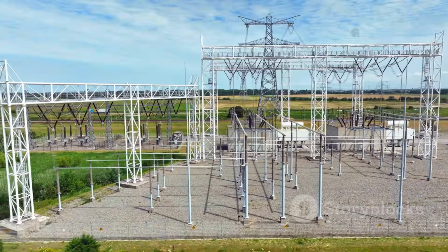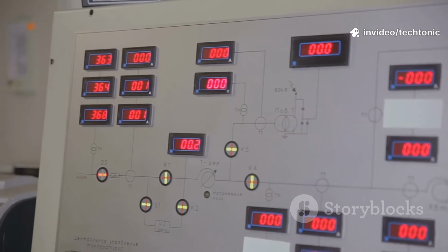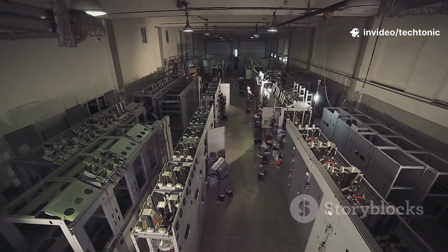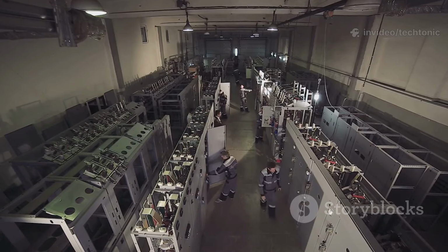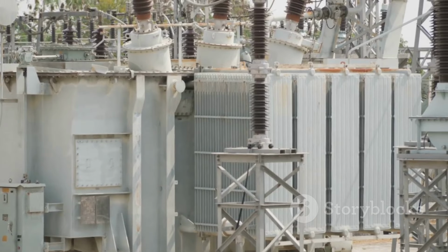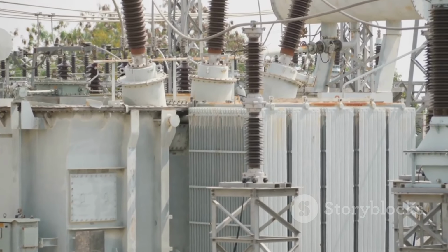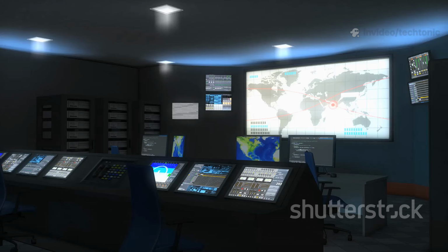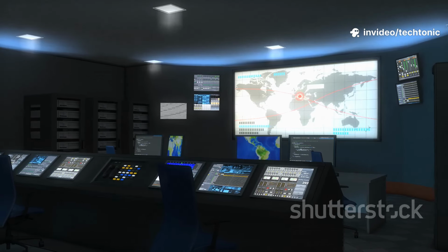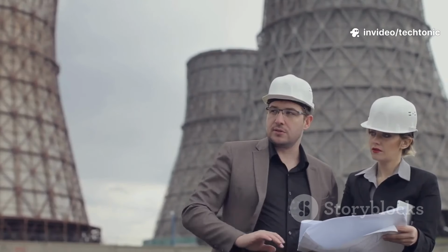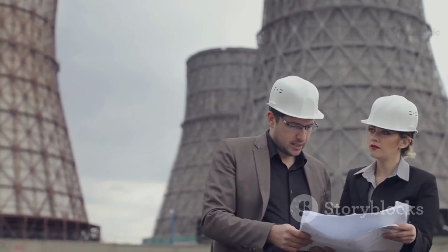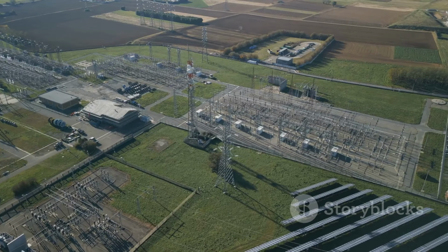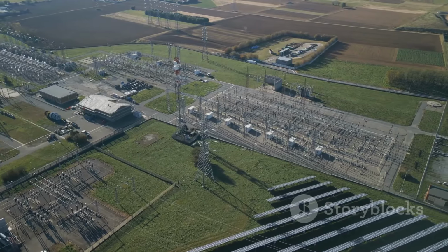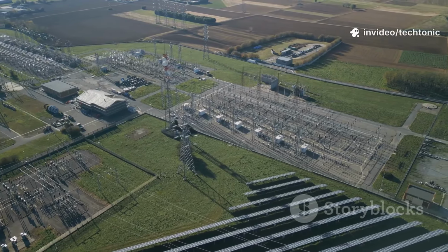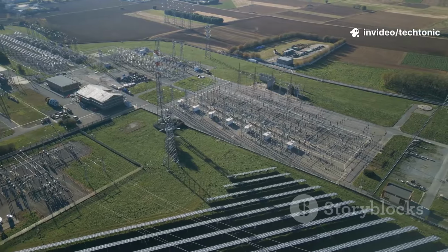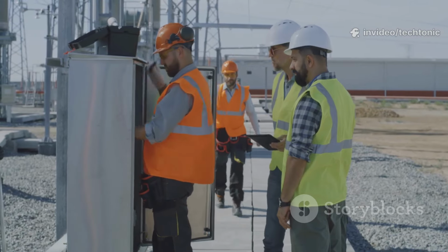These converter stations are the heart of any HVDC system, but they are also its most complex and expensive component. They are filled with transformers, filters to smooth out the electrical signal, and massive halls of power electronics, all requiring sophisticated control systems to operate. This high cost is the primary reason we don't see HVDC lines running to every neighborhood. The expense of building 2 of these giant stations is only justified when the savings from lower power losses over a very long distance are great enough to offset the initial investment. It's a significant upfront cost for a long-term gain in efficiency.